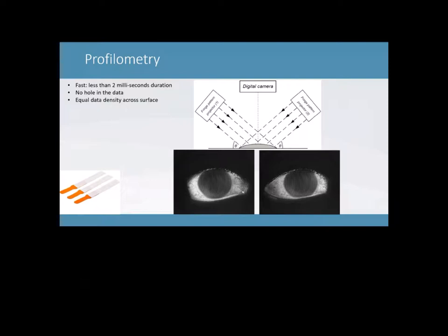So due to the instillation of the fluorescein molecule and the line patterns we project on the eye, the whole ocular surface becomes a reflective area. And we get data on the whole eye that we can gather and get into something for you to read. So we get that data and we translate it for you guys into sagittal height data. So the process of doing this is really fast. It takes about two milliseconds. There's no hole in the data. As you can see, it's completely covered from limbus to limbus. And it's an equal density across the surface.